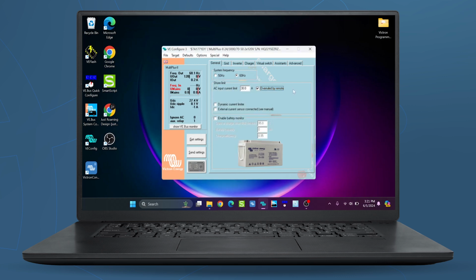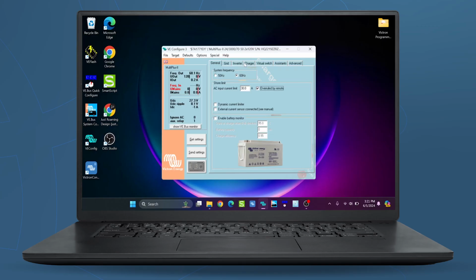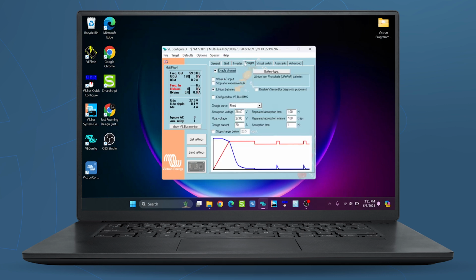However, typically we give our clients the option to dial this up or down on a GX device or using a digital multi-control. Because we're programming this configuration with a Lynx Smart BMS and Smart Lithium Victron batteries, we can skip the inverter tab because the shutdown detection is going to come directly from the BMS, and we want to make sure that the charger is configured to lithium iron phosphate batteries.